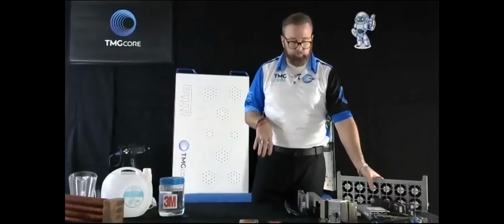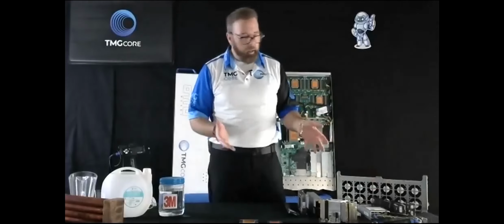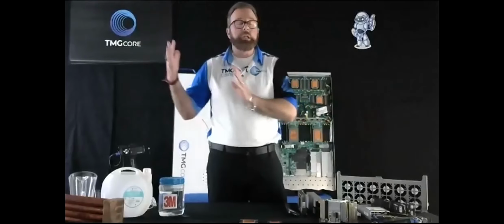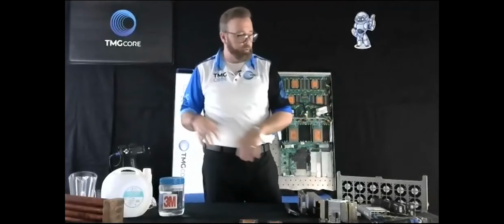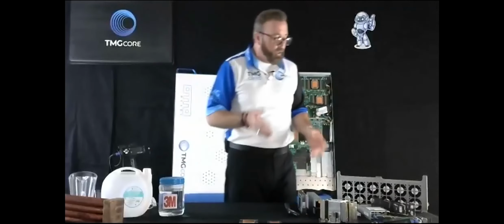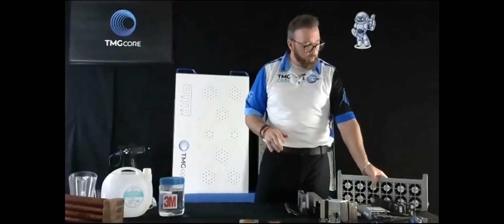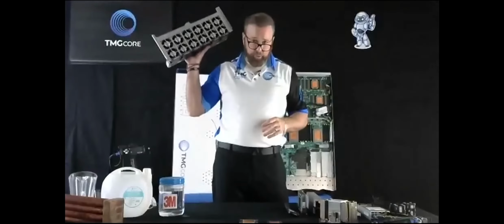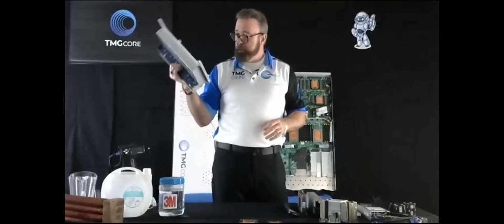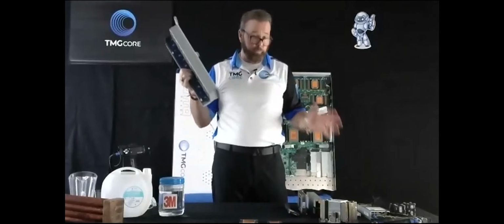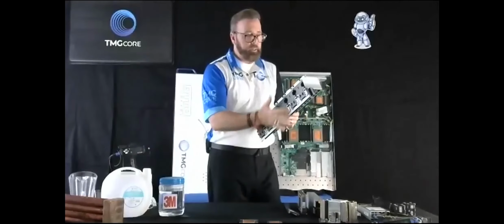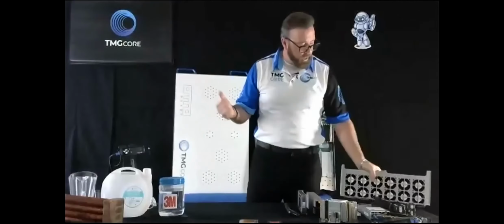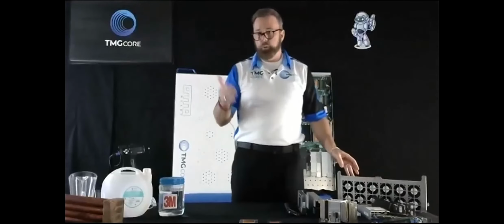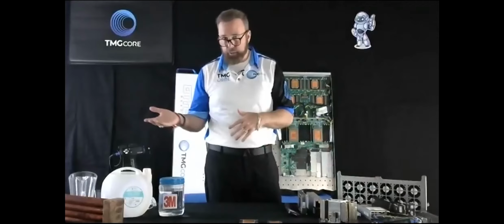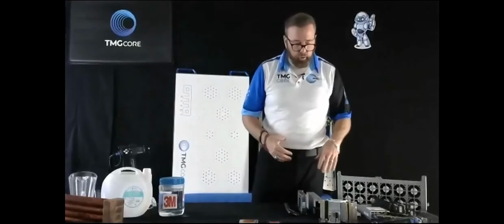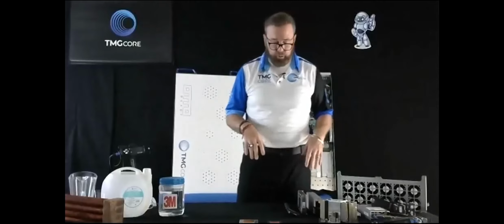One interesting thing is you can get a lot of density. Not what we do from a high performance computing density perspective, but as dense as you're going to get in air cooling, you can get with these things. These are phenomenal. However, something like this uses about 15% of the electricity you need, which makes it very inefficient. These are as efficient as you're going to get with air cooling, but compared to other technologies like liquid on chip, rotary heat exchange, single phase immersion and two phase immersion, these are a lot less efficient, but they've done a great job up until now.